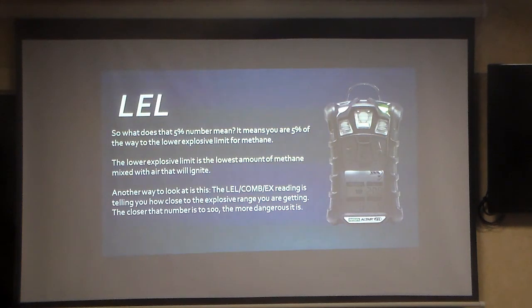If it says 10% of the LEL, you are 10% towards getting to the lower explosive limit for methane, which is methane mixed in air, 5%. Not confusing you yet? So if there is 5 to 15% of this room filled with methane, it is in the flammable range. What the meter's telling you is how close to that 5% you are getting. Right? Does that make sense?